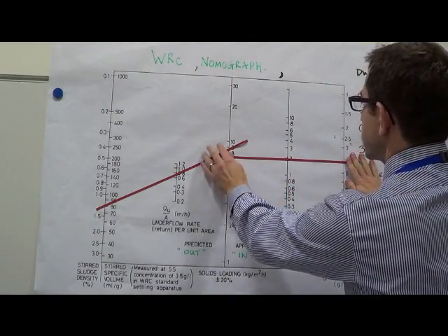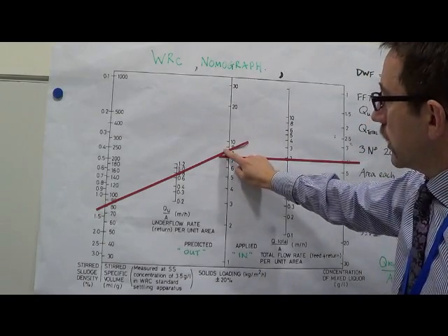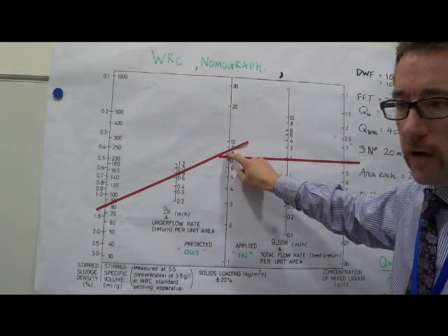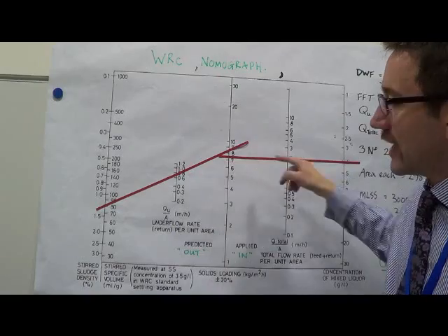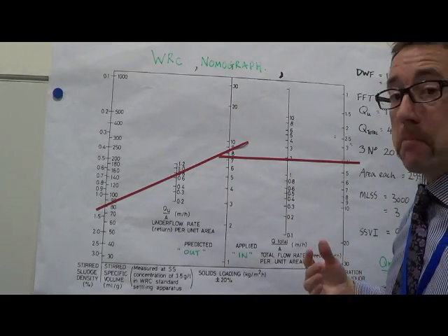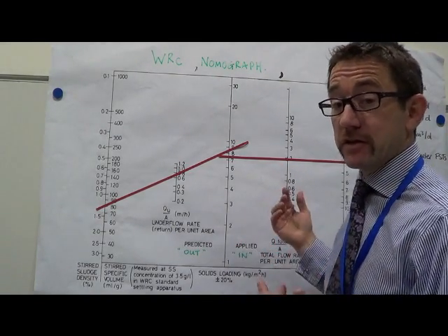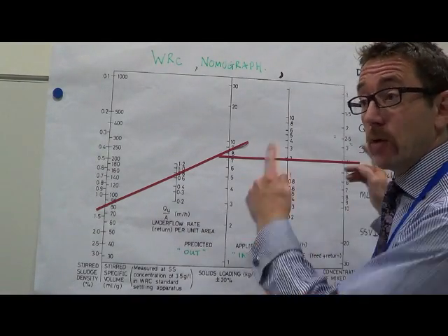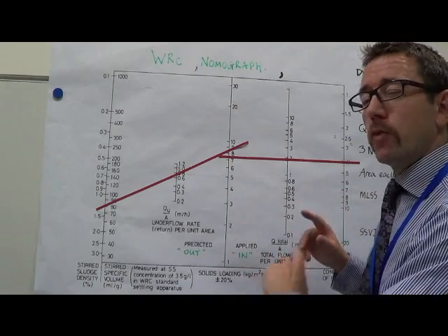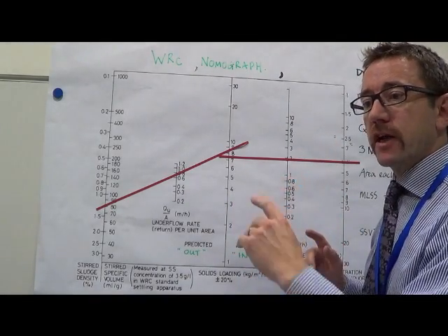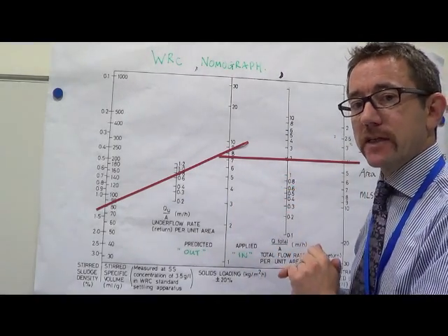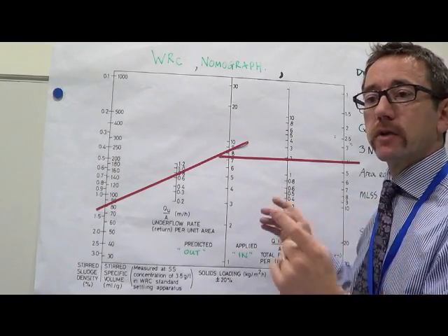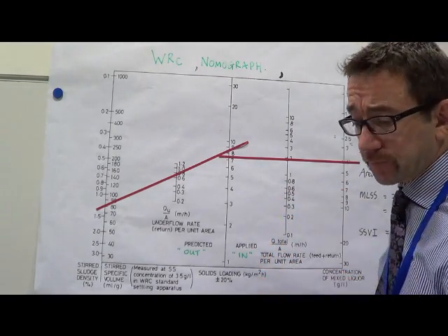I think you can straight away see that, okay, it's still slightly above my line, so I'm still technically okay, but there's a plus or minus on this. That says to me, this site may well have a blanket issue under those conditions. So it's not much of a change, is it? 3,000 up to 4,000 can be all the difference between a blanket carryover or not, which is why it's so important on the golden measures to be really bang on your mixed liquor suspended solids. Of all the things in the world, that's a really sensitive measure.